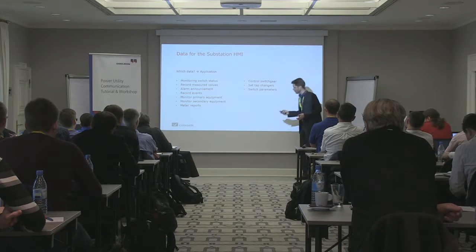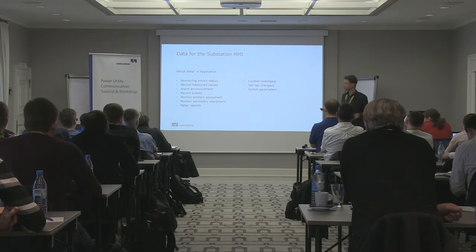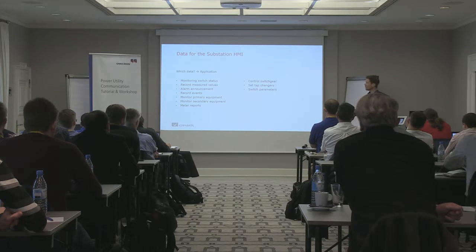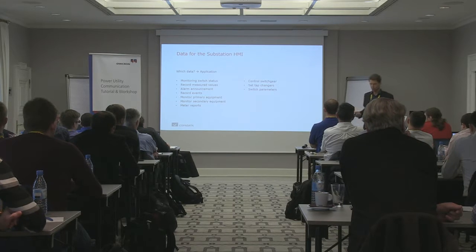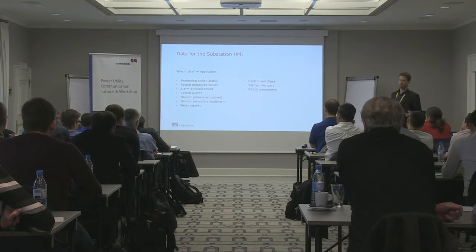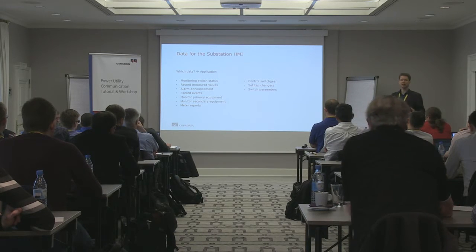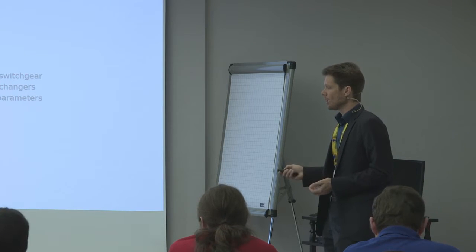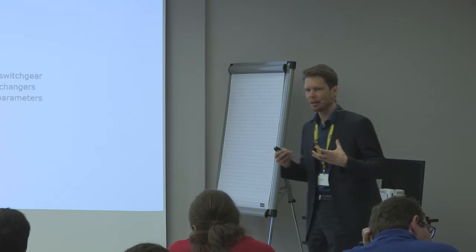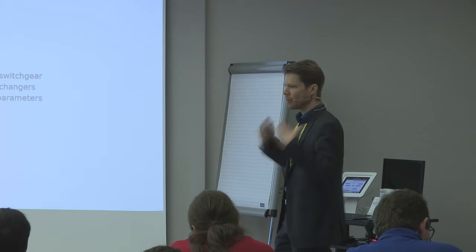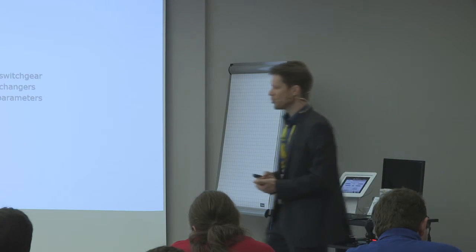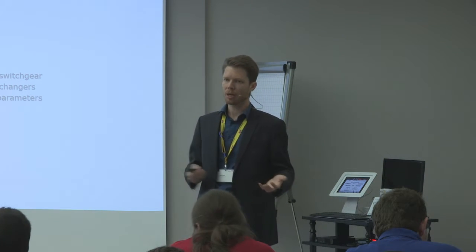There are a few applications: monitoring the switch status, recording measured values, getting announcement of alarms in our HMI. Maybe we want to record the events — not maybe, for sure — because this is the record for if something went wrong. We want to monitor primary and secondary equipment, maybe produce reports and meter reports. So we see this is more about gaining data out of the field. When we say writing into the field, we want to control the switchgear, maybe change the tap position of a tap changer, or just switch parameters in our protection relay.